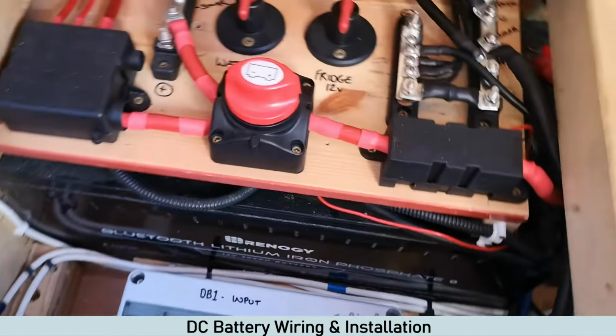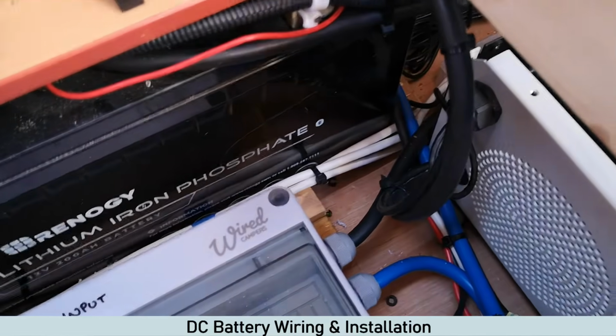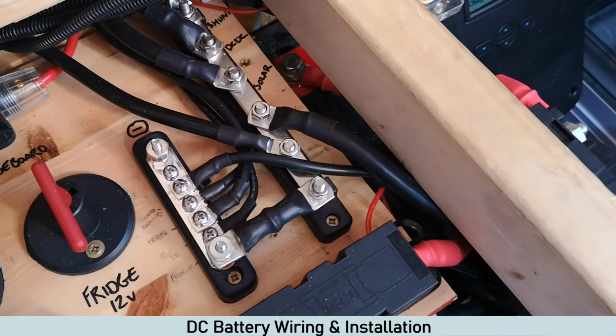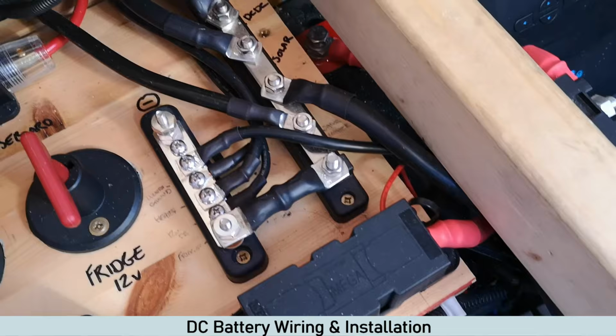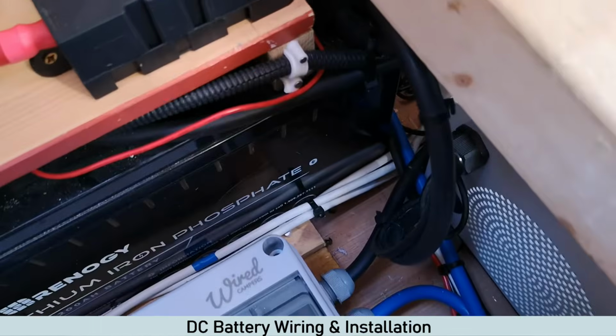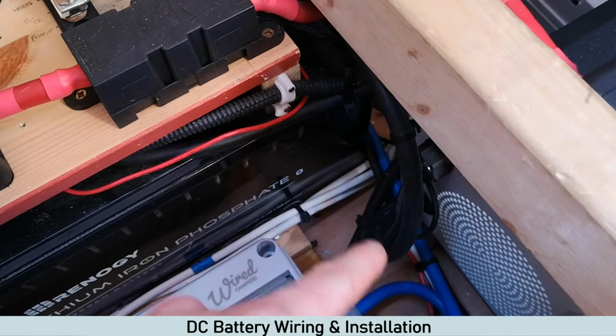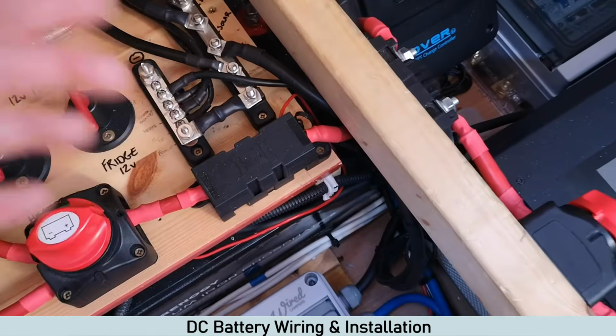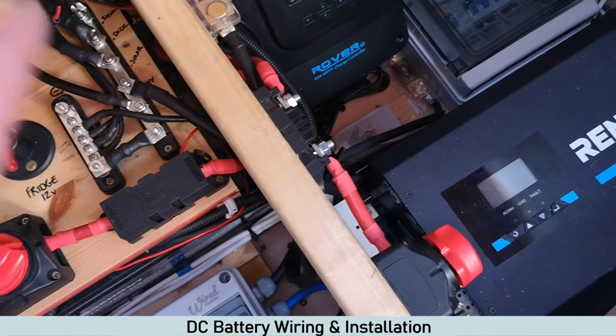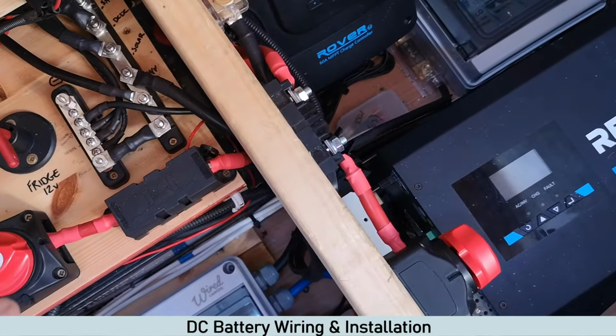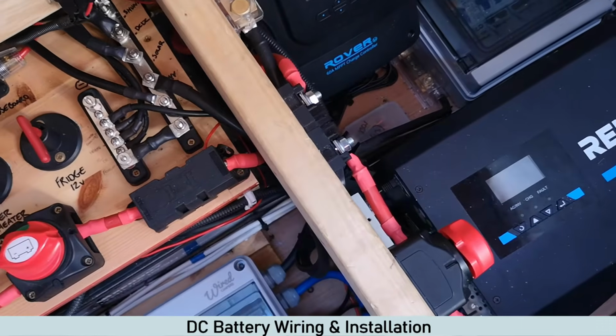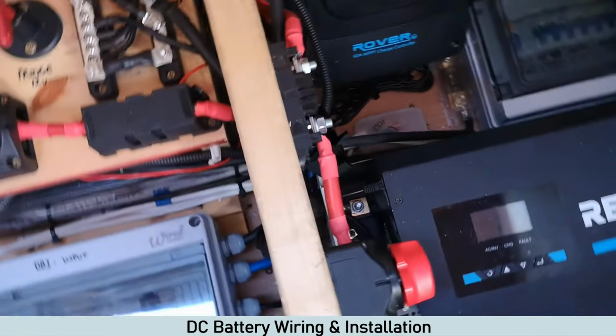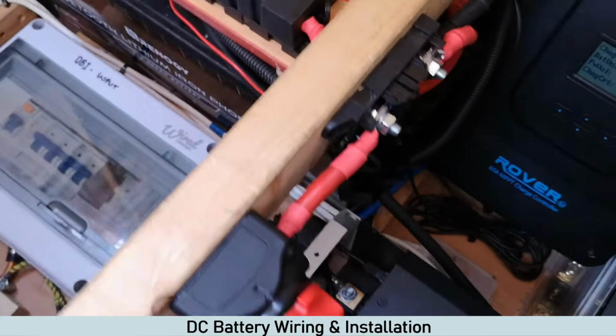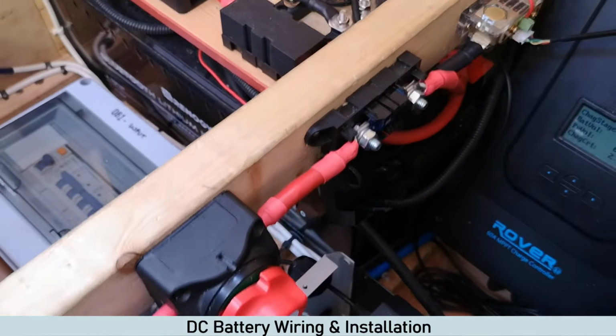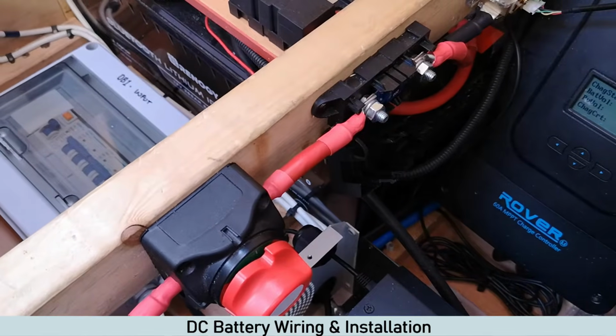And the same goes for the negative. So our negative is 35mm as well. We've done cable calculations as well to work this out, because obviously the length of run, that's only short. But with DC installs, you'd be amazed at how big the cable needs to be if you only extend it by a short distance. So always do cable calculations with any cable you install, just to ensure that the cable can withstand the power.